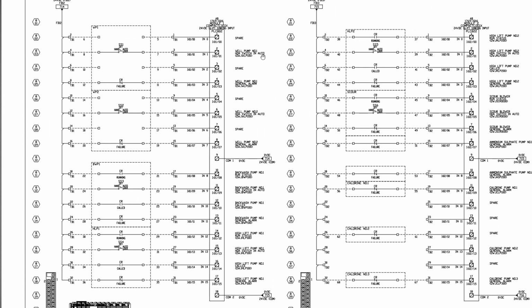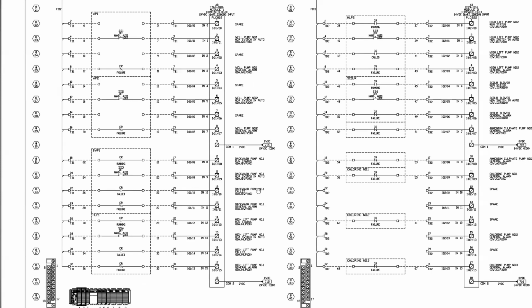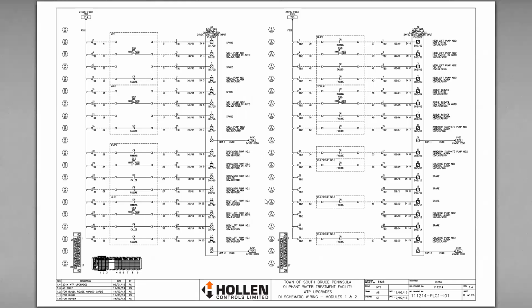We have a spare input, a hand-off-auto switch, another spare input, hand-off-auto switches. If you were reviewing these drawings, it would be very important to make sure that these line up with any IO lists that you have. If you have the PLC program or you're going to be programming it, make sure your program lines up with the IO that's going to be wired.